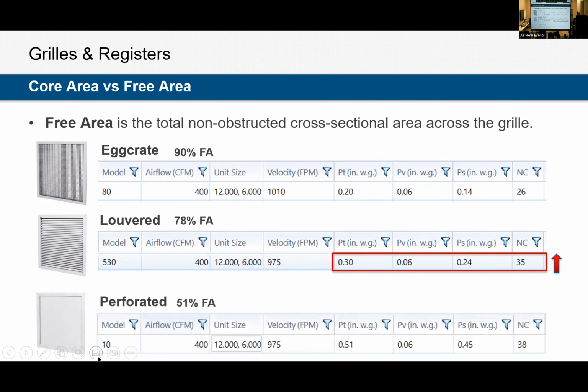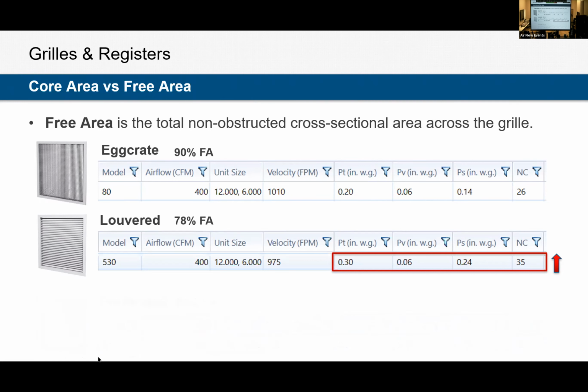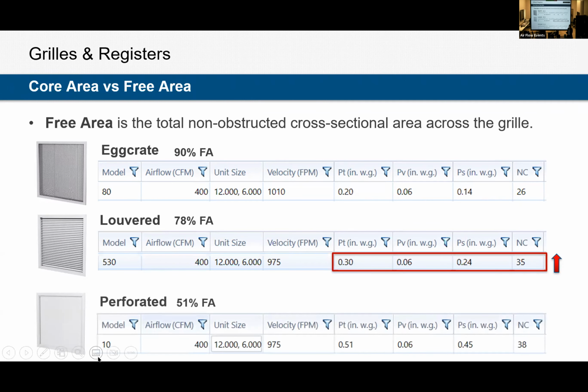Why is the velocity lower? Smaller opening should go faster, right? Correct. Yeah, you're pinching off the airflow, making the air travel faster through it. Because our volume stays the same, but with a smaller opening, it's gonna go faster. Yeah, the louvered one should be a higher velocity then, shouldn't it? Oh, wait a minute. You're right. I don't know the answer to that. What's this one? That one's the same velocity. I think so. So what it may be is actual core velocity. So the core is larger on the louvered than on the egg crate. Is that possible? Does that make sense? So it's not actually calculating your free air velocity, it's your core velocity. Yeah, potentially. That would make sense, because you would have to have the air measurement upstream in that port.